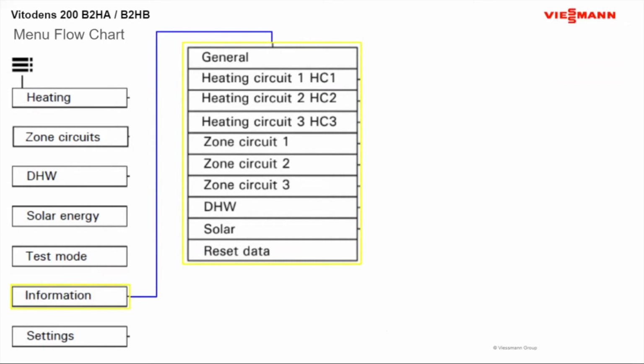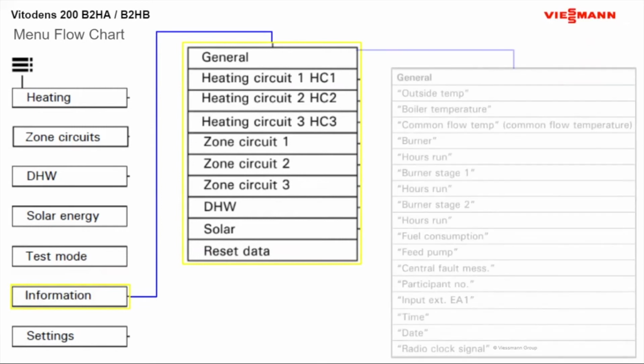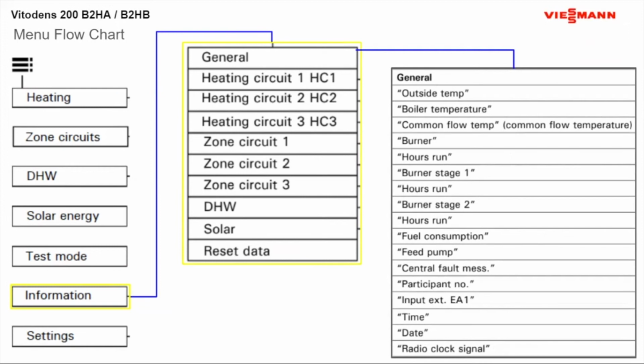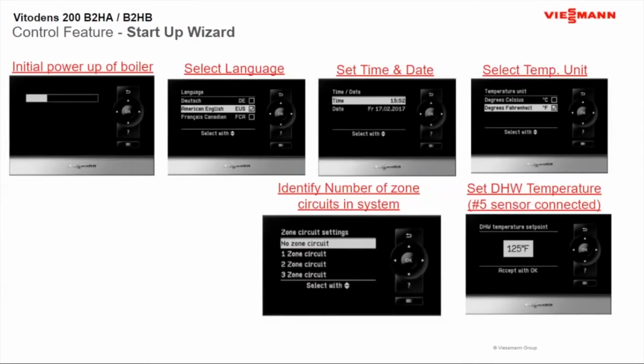The information button is just to see what the different circuits are doing. If you hit the general button itself, the submenu will come up here, and it will give you your outdoor temperature, your boiler temperature, your run hours, things to that nature. Talk about the startup wizard a little bit here.